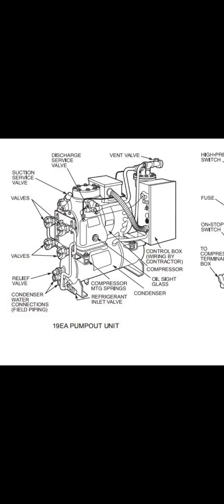Now you see the valves, these are 4 valves. Alternatively, they will change oppositely. So what you will do is reverse the cycle of refrigerant. You take the refrigerant suction line and discharge into the condenser. Before it was taking from the condenser, now it is taking from the evaporator. The vapor suction is taken from the evaporator and discharge is given into the condenser.